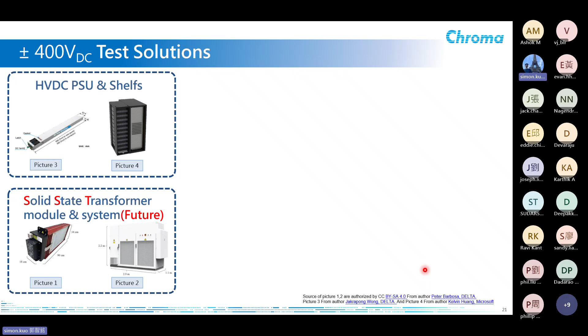So basically, for the high voltage loads, because it's DC only, it either converts from AC to DC or from DC to DC. For the AC side, it's the same as the previous slides. For the DC loads, we have the linear one, the 24A 1200 volts, so the maximum you can reach is 1200 volts. The benefit is that it's a very high slew rate linear load, which can achieve 24 amps per microsecond. And as I mentioned, they might need to do a long time testing or burn-in test.